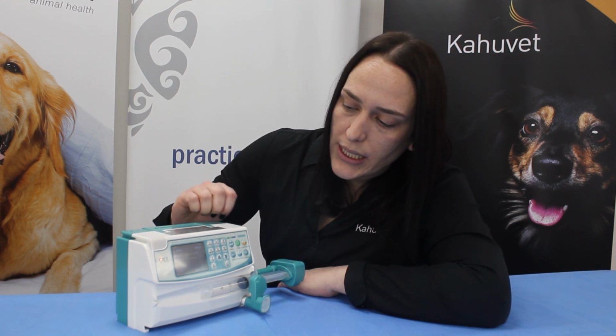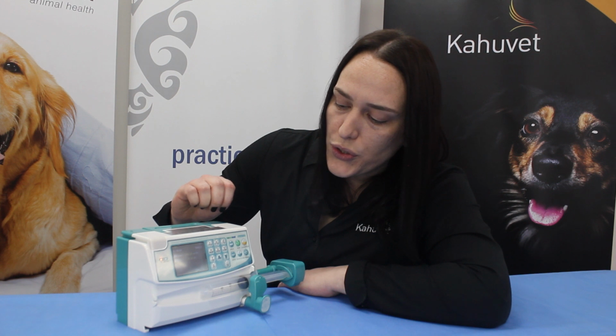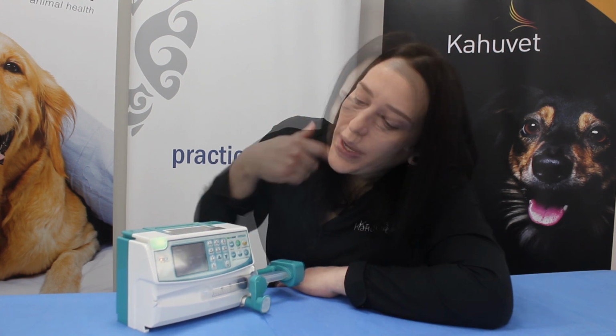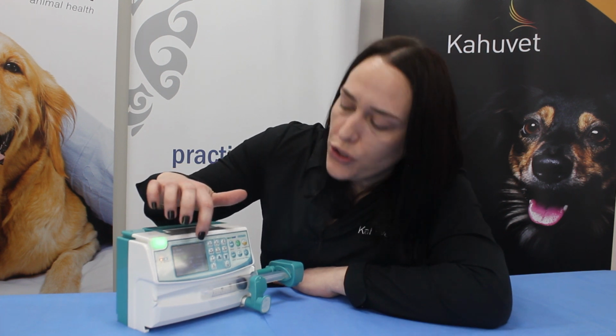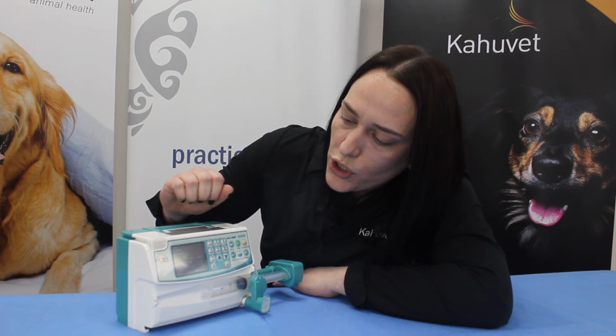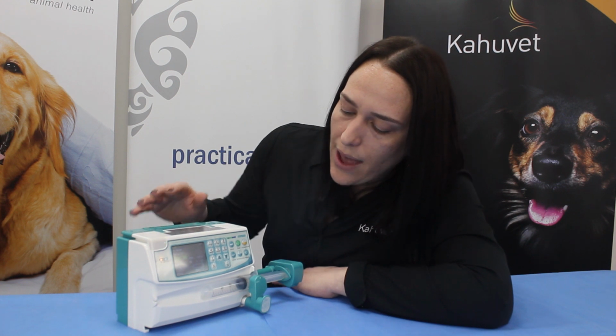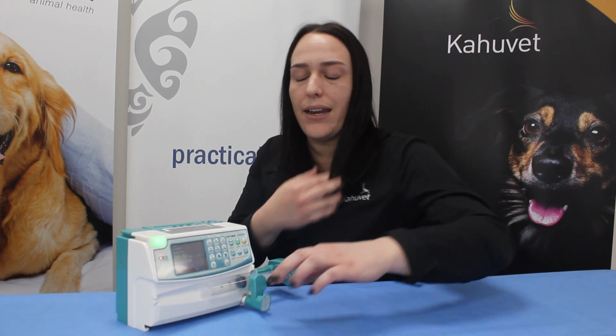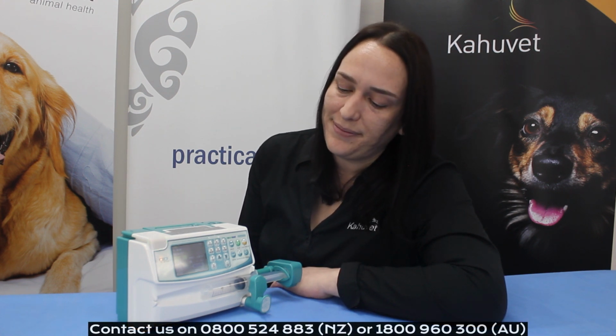Now that we've got that all set up with our rate and volume to be infused, we can press our start button to start the infusion. We can see our total for the infusion is about 3 minutes here, so we'll just wait for that one to finish. And what we're hoping to see is the syringe expelled down to the 10 mil mark and finished exactly on that 10 mil line. We do allow a discrepancy of 0.5 mil, but anything outside of that, then please do contact us so we can support you through this one.